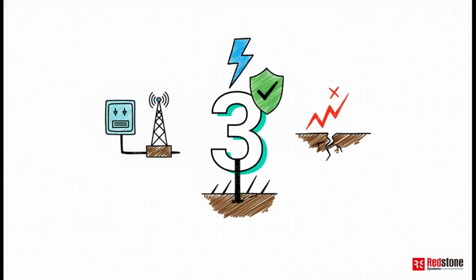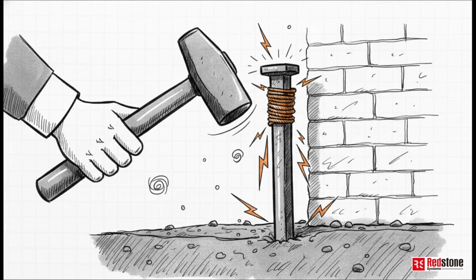This right here is arguably the most important metric of your entire electrical installation. Your resistance to the ground must be less than or equal to 3 ohms. It needs to be grounded separately and thoroughly, fully complying with standard communication equipment grounding rules. If your resistance is tracking higher than 3 ohms, your system is highly vulnerable. But what if you are deploying in an older building that completely lacks proper standard grounding conditions? Well, the manufacturer explicitly outlines emergency grounding tactics for this exact scenario.